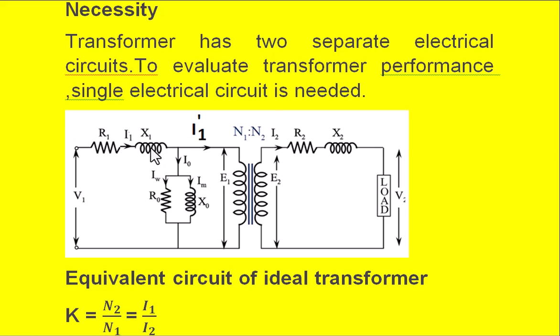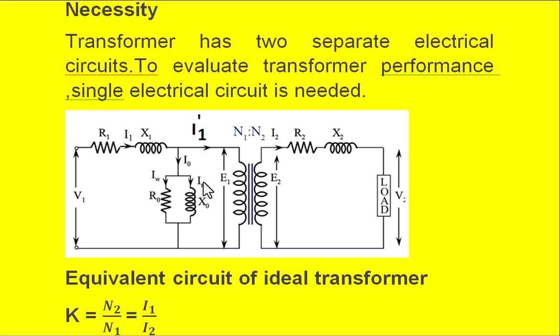I0 is the no-load current of the transformer. The no-load current components are the real power loss component Iw (or Ic) and the magnetizing current component Im, which passes through X0 (also represented as Xm). This is the magnetizing reactance, and R0 is the core loss component.